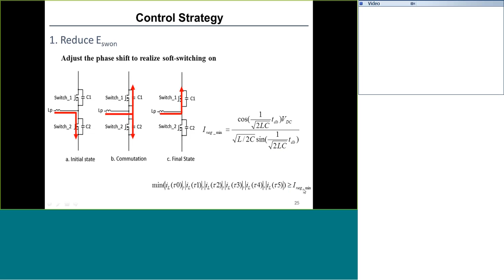When we do the calculation, we need each turning point of the transformer current to have an absolute value larger than this minimum required current. Otherwise, the switch will lose zero voltage switching. Now, what values should we select for this minimum current?